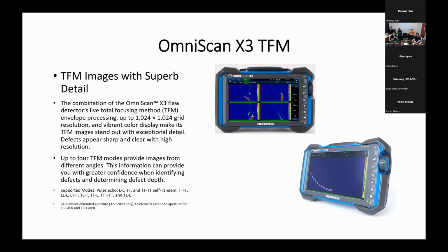So one thing we have available on the X3 is TFM. It's the total focusing method. It's a combination of OmniScan X3 flaw detectors and live total focusing method, with onboard processing up to 1024 by 1024 grid resolution. Its vibrant color display makes TFM images stand out with exceptional detail. The details are very sharp and clear with high resolution. You can run up to 4 TFM modes to provide images from different angles. That information can help provide greater confidence when identifying defects and determining defect depth.